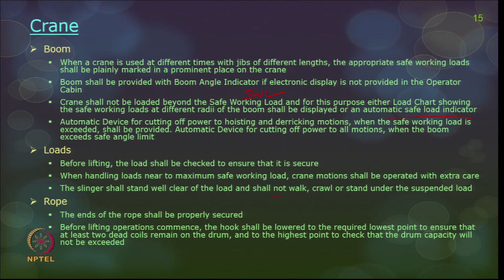Rigging practices: lifting equipment and slings shall not be overloaded. Erection shall be carried out only in daylight, and all rigging hardware below the boom point is considered as load acting on the crane. It shall be noted that the shortest sling leg can carry more load. So, you can also determine the crane load, and the hook capacity or the sling capacity can be determined with the load chart, which is available from the crane manufacturer.